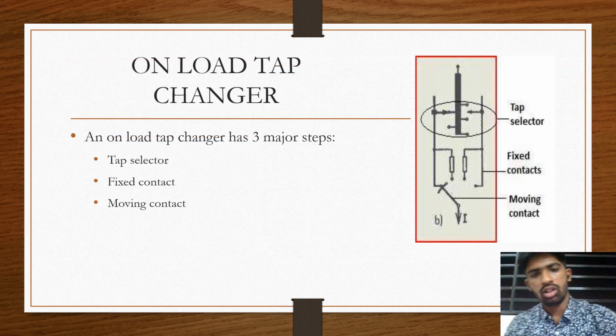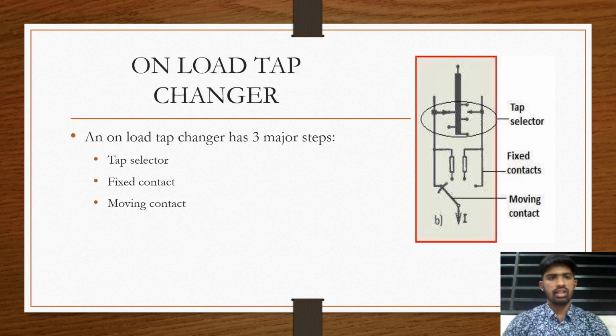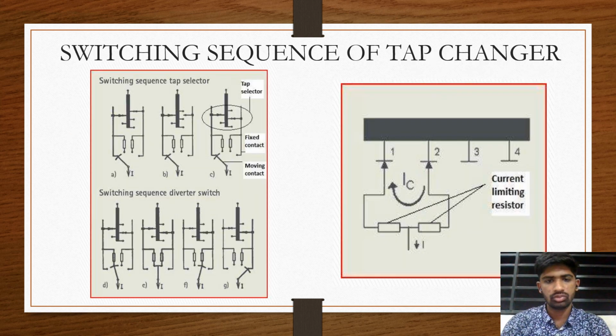Moving on, we'll see what an on-load tap changer is. In this type of tap changer, we have three major parts: the tap selector, the fixed contact, and the moving contact. The tap selector is used to select the appropriate taps. The fixed contact is used to hold a fixed position, and the moving contact moves to open or close the appropriate taps. We have a picture on the right side to identify all these three different parts.